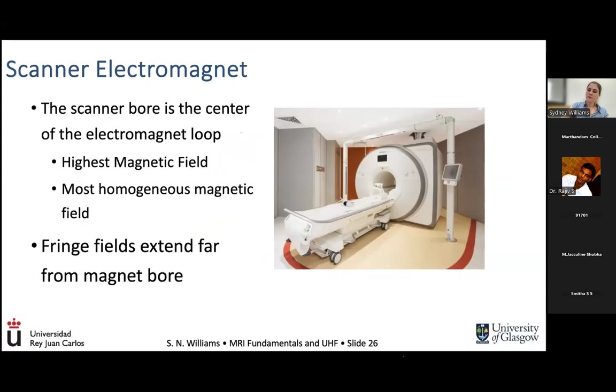But again, we want it to be a high field because why? We actually produce more signal that way. So if you remember back to the conversation of SNR, how high resolution we can reasonably acquire with MRI is related to the amount of signal available. If we increase this magnetic field strength, we'll have inherently more signal available, and that will be a motivation to go to higher fields. Or is it? See, this is again the challenge with all medical imaging, and MRI in this case, is that when we do get higher field strengths, we also have more challenges.